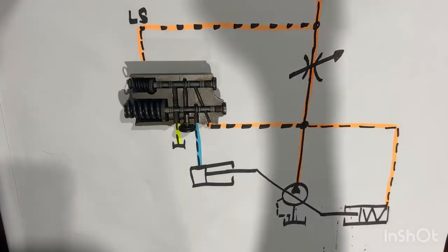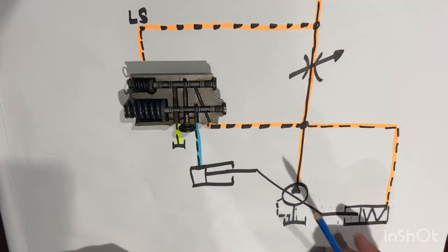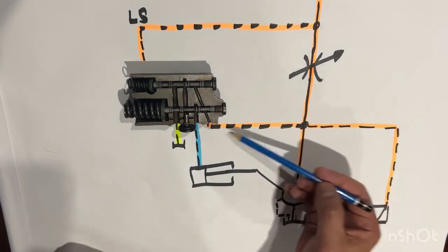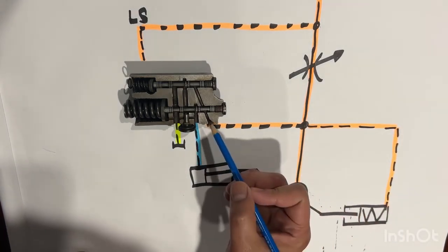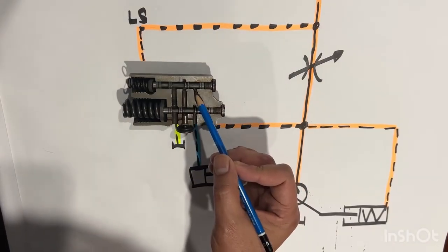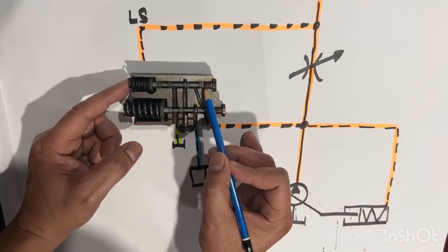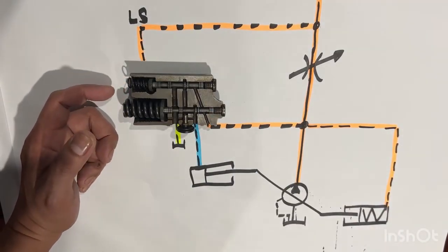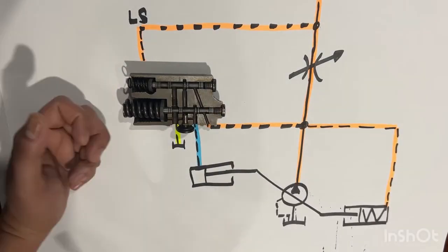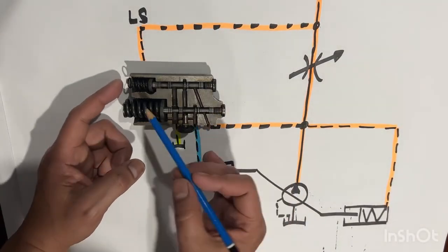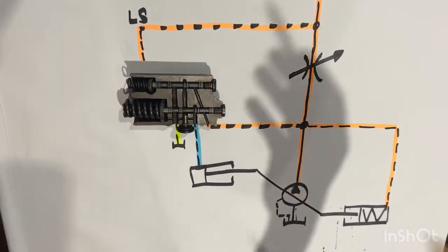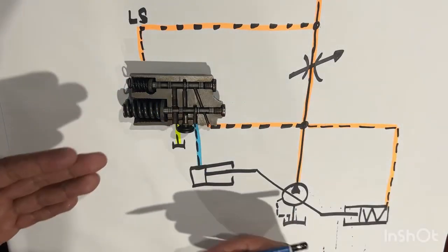What happened here is the pump, because the pump is in a max stroke, will displace flow and then create pressure. Now this gallery here is the system pressure. Okay, now the pressure is acting on the spool. What happened? Because the pump is a positive displacement pump, it will create infinite pressure if you don't limit that pressure. But this spring is set only to 15 bar delta P, but this is the standby mode condition.